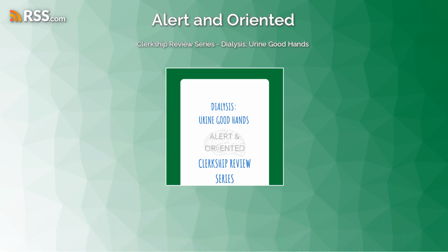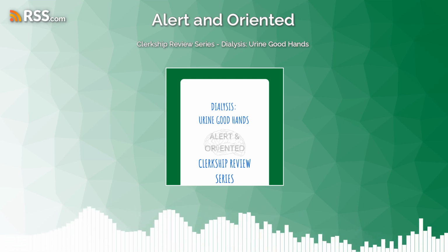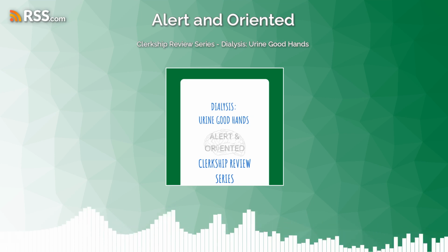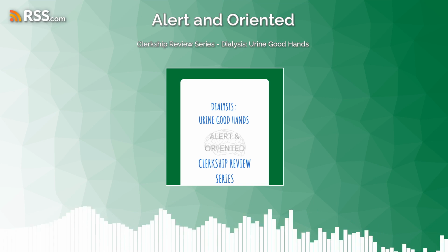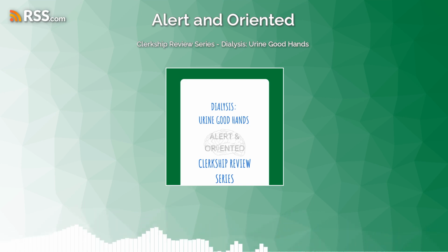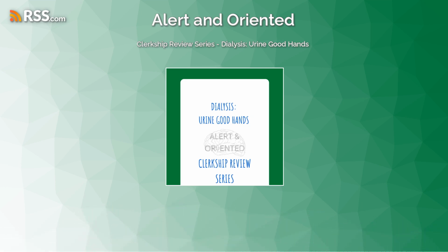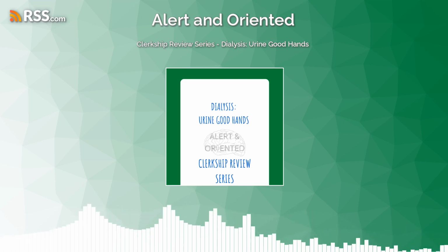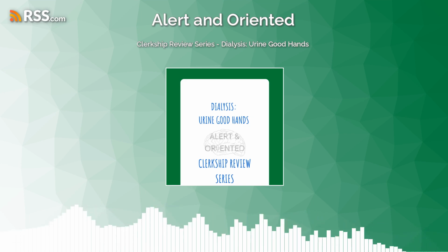Certain institutions use that modality because they have staffing limitations. For example, when COVID happened, because of the septic shock that was associated with COVID in the first round of COVID, we had a significant number of patients who developed AKI due to septic shock, and a lot of people required dialysis. And if you have a limited number of staff and a limited number of machines, instead of doing a treatment for 24 hours with one machine, you could actually do 2 10-hour treatments during a 24-hour period. So you can actually dialyze double the number of patients.